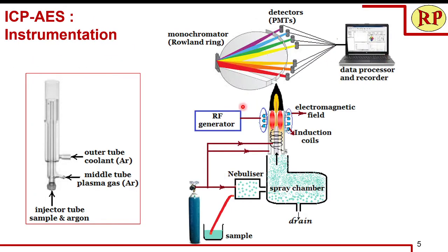In the instrumentation, we have an argon cylinder and a sample. The sample enters the nebulizer along with the argon gas and gets converted to the aerosol mist. This enters the spray chamber where fine particles along with argon gas enter the center tube of the plasma torch, while heavy or larger particles are drained at the bottom.